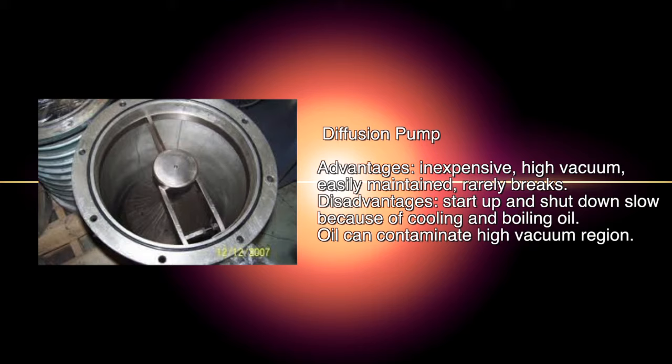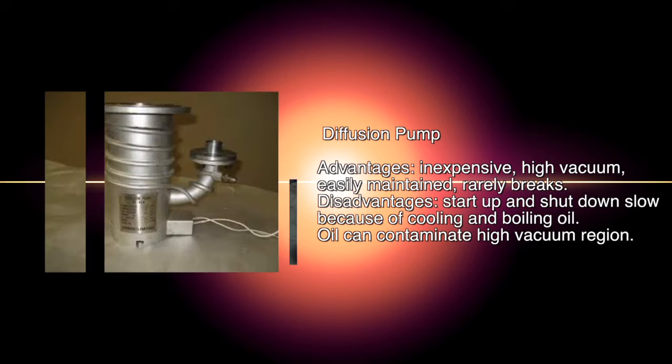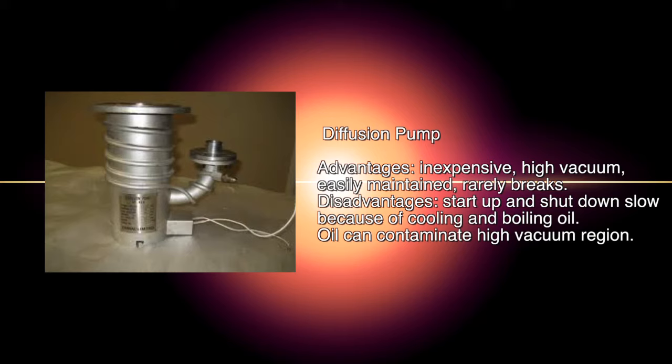The advantages of this particular diffusion pump is it's very inexpensive, it can reach high vacuums of 10 to the minus 10 millibar in some cases, and it's really easy to maintain. However, there are disadvantages: it has a very slow start-up and shut-down procedure because of the cooling and boiling of the oil, and the oil can contaminate high vacuum regions.